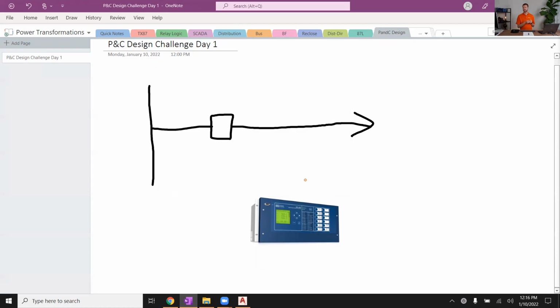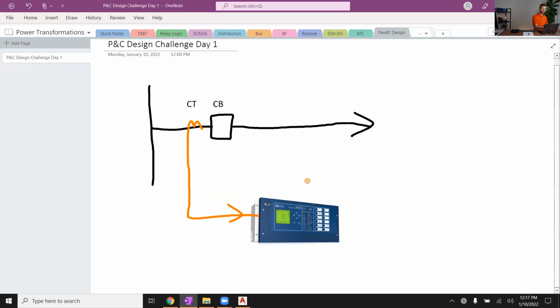Typically, a lot of times we'll pull those CTs from our circuit breaker bushing CTs. And so remember, the square is a circuit breaker. And I'm showing you that arrow to show you the flow of information here. So I'm going to write CB, that's for circuit breaker. This is our CT. I'm going to add another very important thing to our CT, though, that we'll talk about a good bit in this course. And that is polarity dots on the primary side and on the secondary side. We'll get into what those polarity dots mean later on, but that's important. Anytime you're drawing CTs on a one line or a three line on an AC elementary, you want to be aware of your polarity dots.